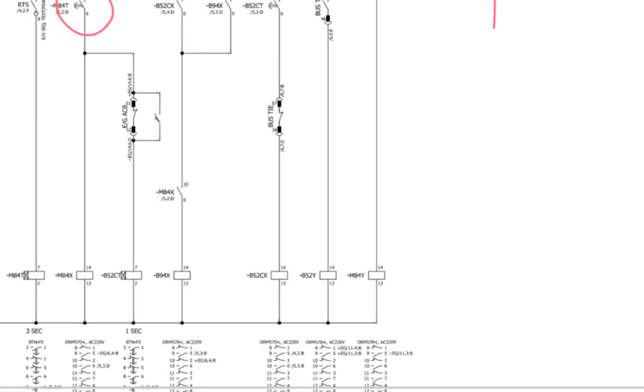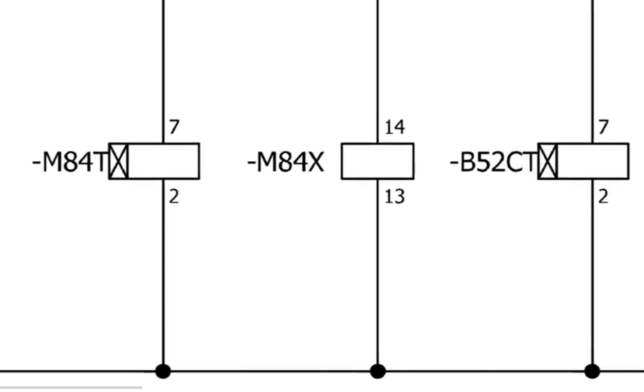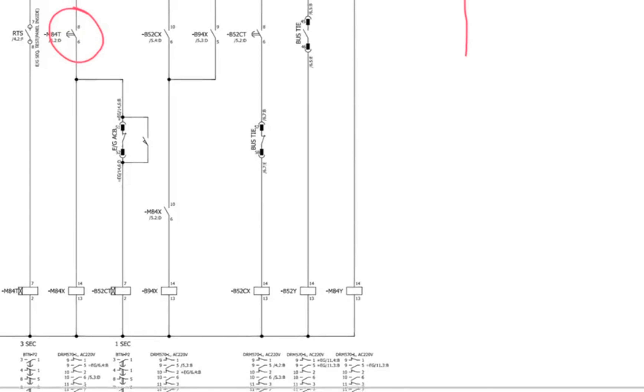So the issue is the timer — the M84T on-delay timer is defective. Luckily we have the same timer as a spare. We will replace it and check the circuit again, then take the emergency generator on load once more.